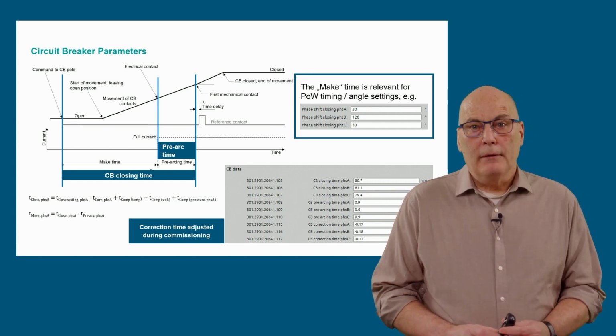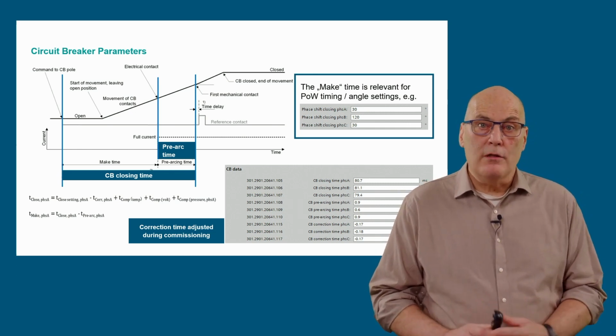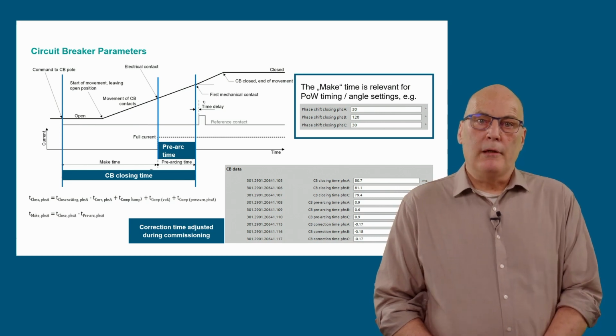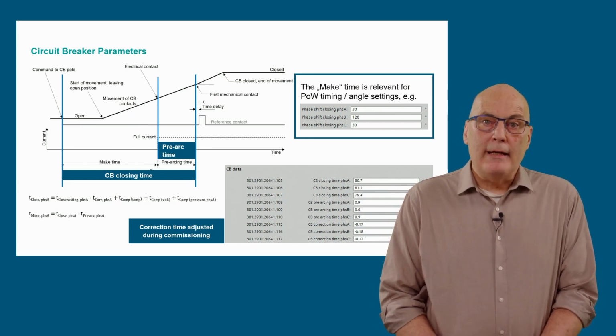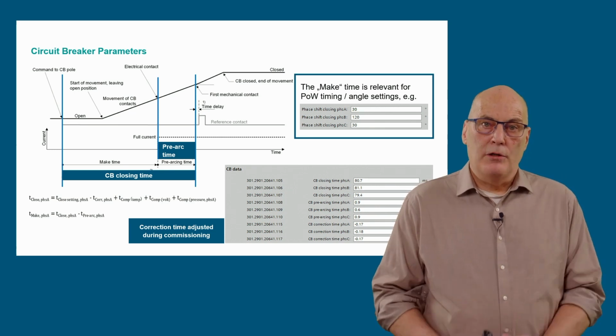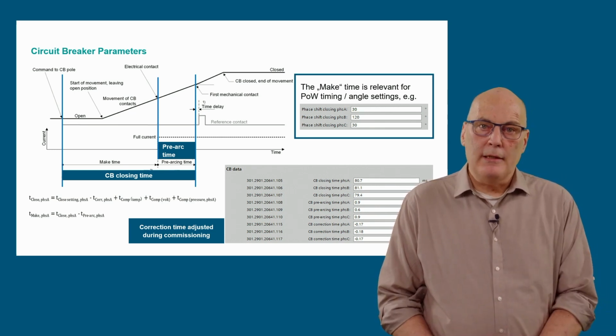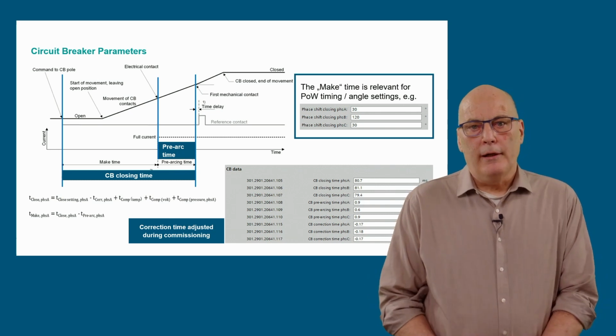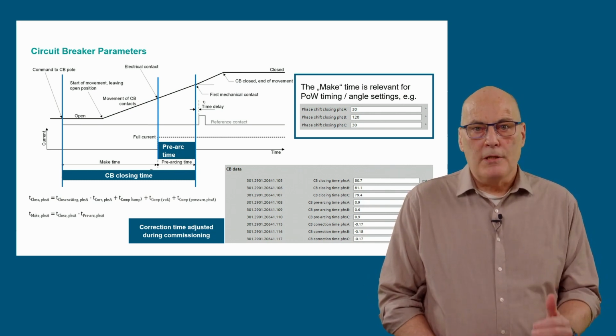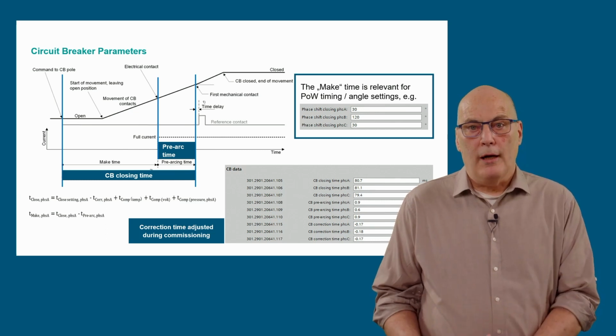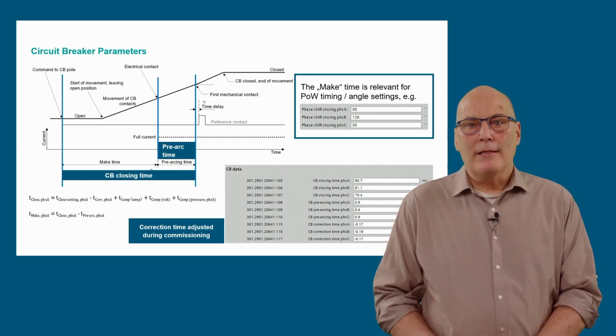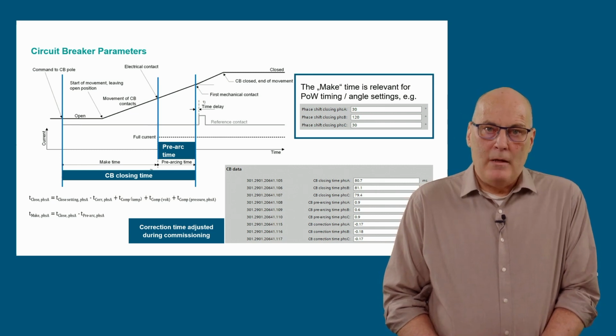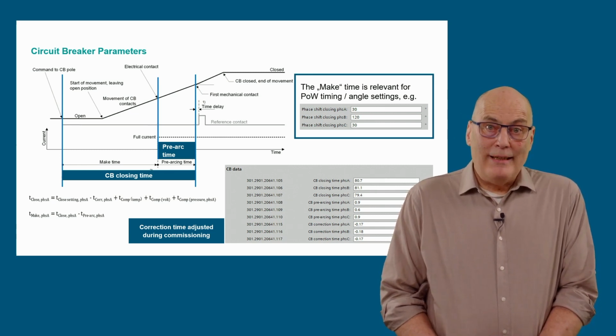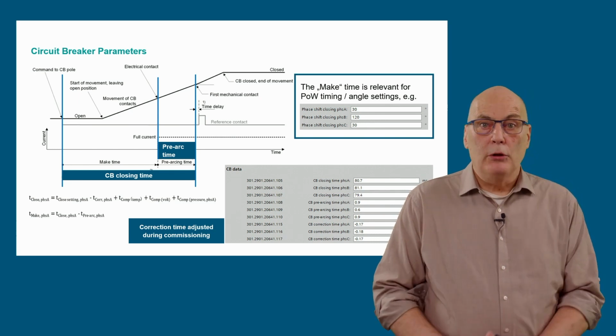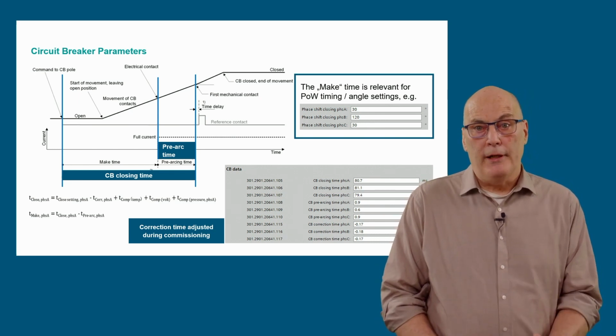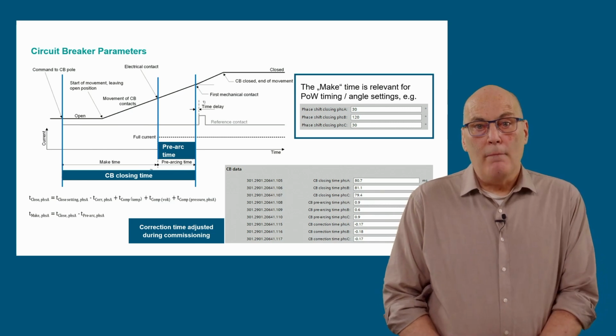The equation that calculates T close phase A, shown directly below the CB closing time bar in the diagram, indicates this. Based on the set closing time as done in the CB data settings, the actual closing time is calculated as shown in the equation by considering the influence on closing time, transducer inputs, as well as the set correction time. This correction time setting is the key parameter for adjustment during commissioning, as will be shown in Chapter 3. Initially, the correction time would be 0.